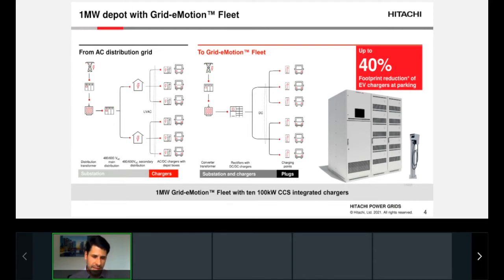It consists of a common AC to DC rectification block in the middle of the chart, which creates a common DC bus shared to DC-DC converters stacked into racks. The key element is common DC power sharing within the cabinet, avoiding distribution across a typical low voltage connection, which requires a whole lot of equipment, cabling, and installation upstream. So we're condensing and simplifying the overall system and power conversion to enable an optimized footprint, an optimized system, and a scalable solution.